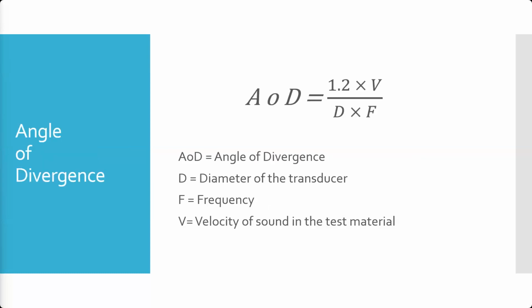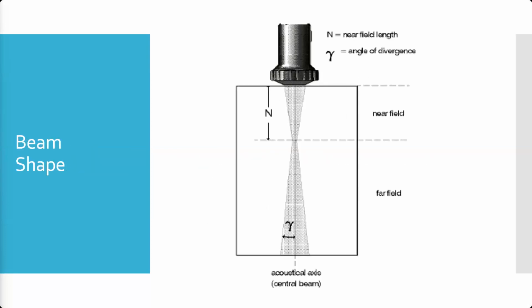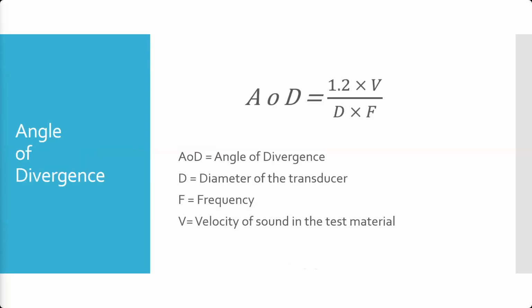Okay, next one is the angle of divergence. So using the same example, velocity of 5,100 meters per second, frequency of 1 megahertz, diameter of our transducer 0.5 centimeters. What's our angle of divergence? And just a quick note on here, remember the angle of divergence is half of, is from the central axis, the acoustical axis, so straight down from the probe. So if you're trying to figure out the full width, it's going to be double that angle of divergence. Okay, but typically angle of divergence is taken from the acoustical axis to the edge of the wave. So velocity of 5,100 meters per second again, frequency of 1 megahertz, diameter of our probe 0.5 centimeters. What is our angle of divergence?